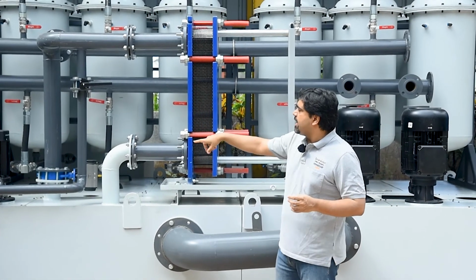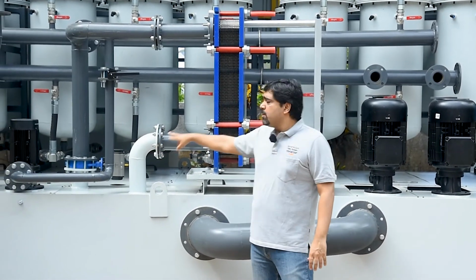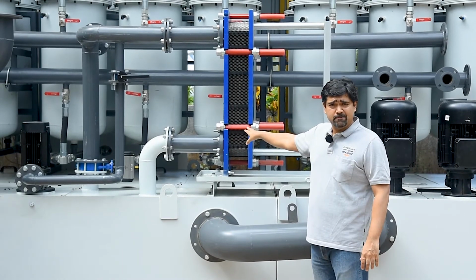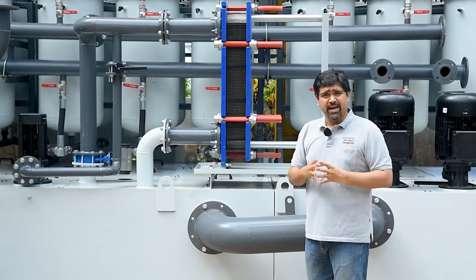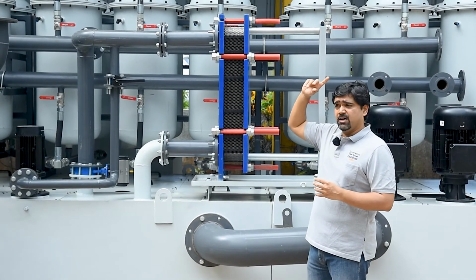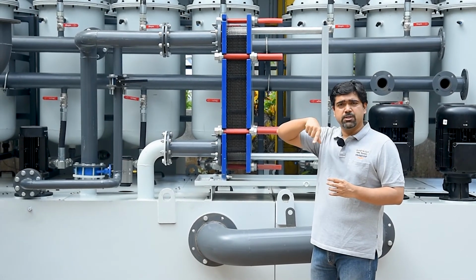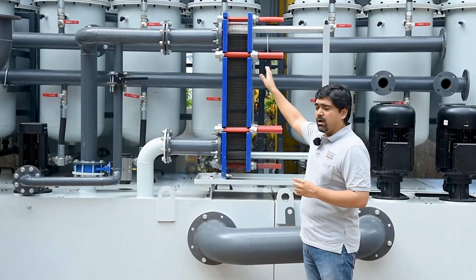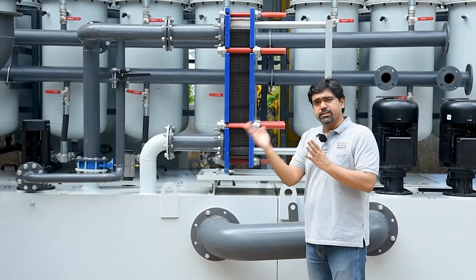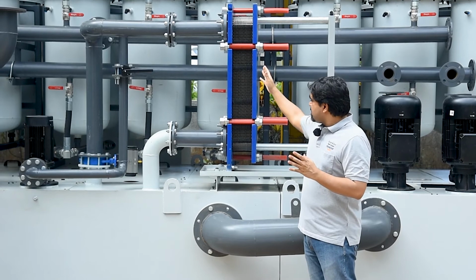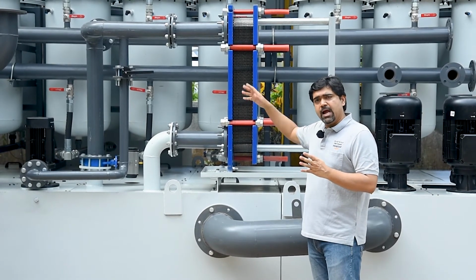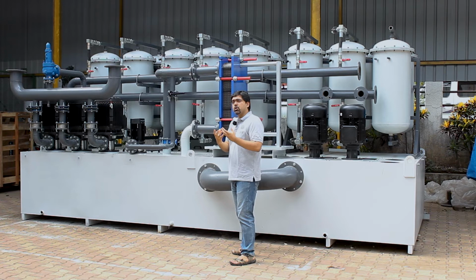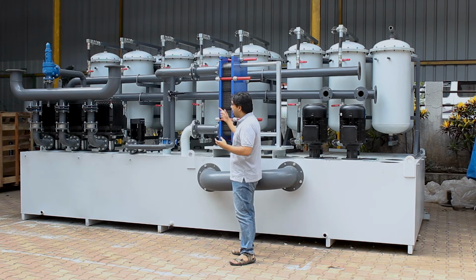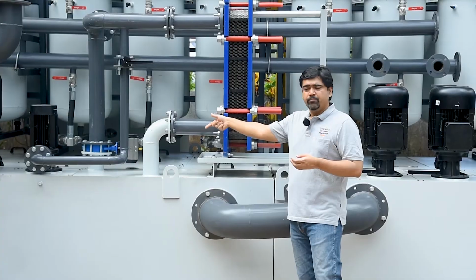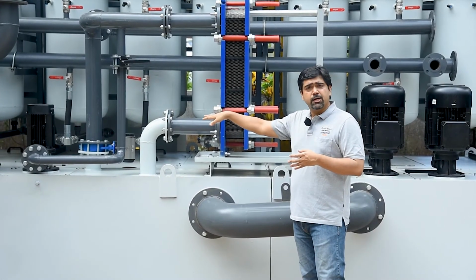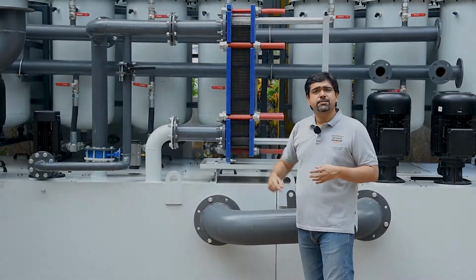So on one side, through this pump, the clean oil will be pumped through this plate heat exchanger. So that becomes the hot side of the plate heat exchanger. And the cooling water from the cooling tower at the customer's location will come on the other side. So that becomes the cool side. And the heat transfer will happen inside this, and the temperature-controlled, or rather cool, oil will again be collected in the clean oil compartment. And that temperature-controlled cool oil will be supplied to the machines.